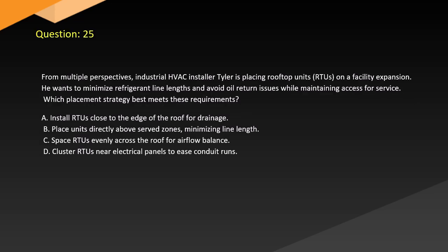Question 25. From multiple perspectives, industrial HVAC installer Tyler is placing rooftop units, or RTUs, on a facility expansion. He wants to minimize refrigerant line lengths and avoid oil return issues while maintaining access for service. Which placement strategy best meets these requirements? A. Install RTUs close to the edge of the roof for drainage. B. Place units directly above served zones, minimizing line length. C. Space RTUs evenly across the roof for airflow balance. D. Cluster RTUs near electrical panels to ease conduit runs.